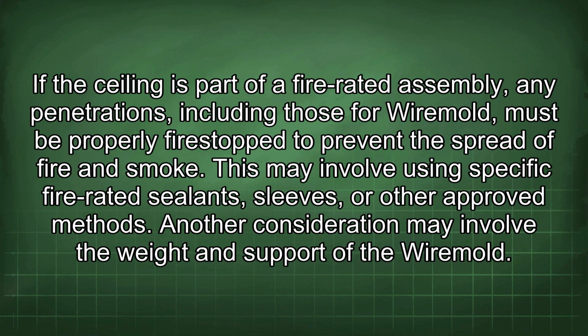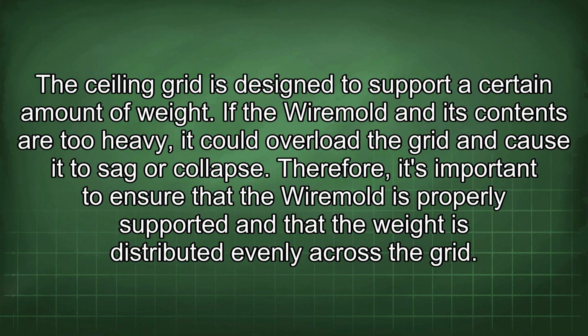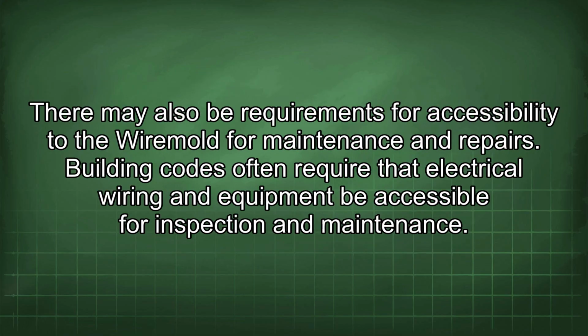Another consideration may involve the weight and support of the Wiremold. The ceiling grid is designed to support a certain amount of weight. If the Wiremold and its contents are too heavy, it could overload the grid and cause it to sag or collapse. Therefore, it's important to ensure that the Wiremold is properly supported and that the weight is distributed evenly across the grid. There may also be requirements for accessibility to the Wiremold for maintenance and repairs.